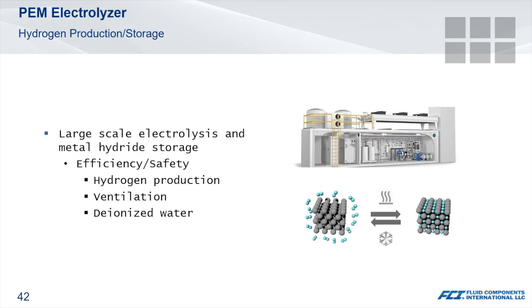There is a growing demand for the use of proton exchange membranes for electrolysis, given its roughly 80% electrical efficiency. Combined with metal hydride storage in a fuel cell, you have a great source of green energy. Its ability to adapt to dynamic loads is another reason for growing preference and can require flow instruments with broader turn-down ratios. In addition to measuring hydrogen production, safety-critical applications can include the monitoring of ventilation air and deionized water.